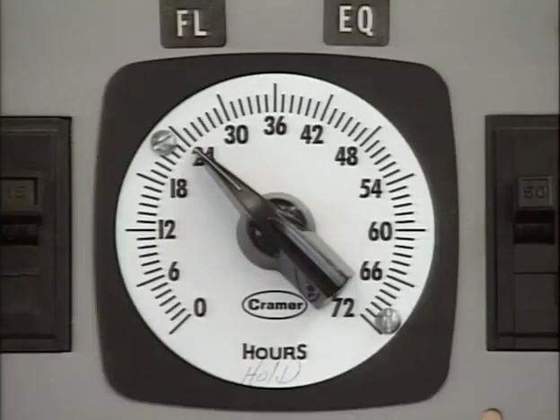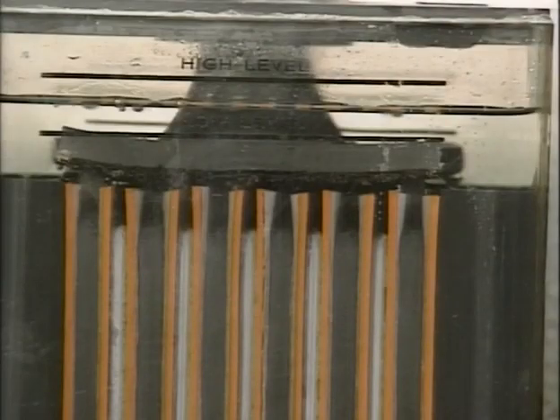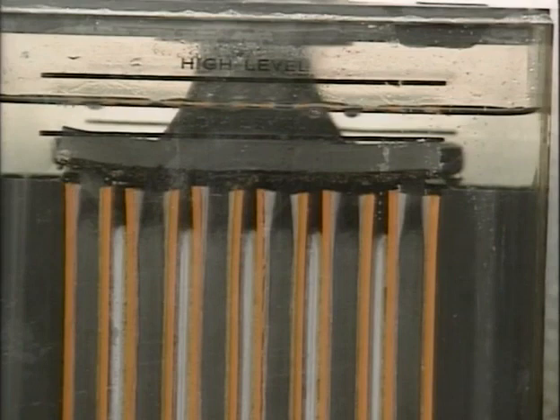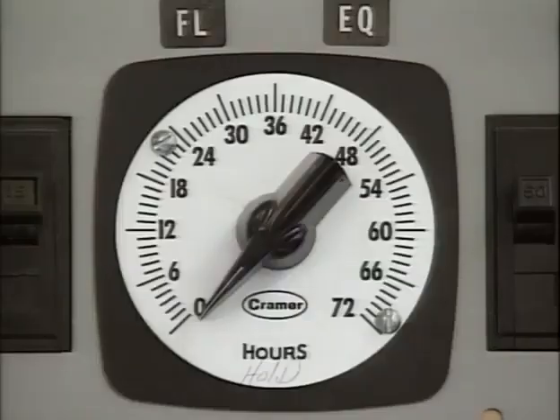In addition, specific gravity readings should not be taken during or immediately after a battery is given an equalizing charge. The reason is that it takes time for the sulfuric acid from the plates to mix with the electrolyte, so the specific gravity will continue to increase for a period of time after the cells have been fully charged. For this reason, specific gravities should not be checked until the battery has been on normal float charge for at least 72 hours after an equalizing charge.